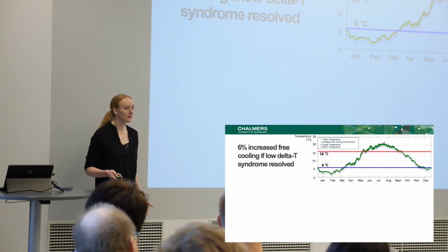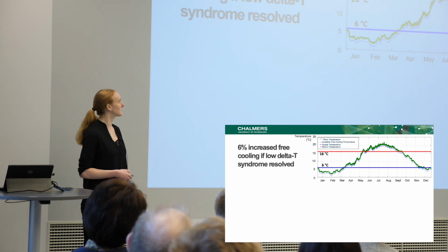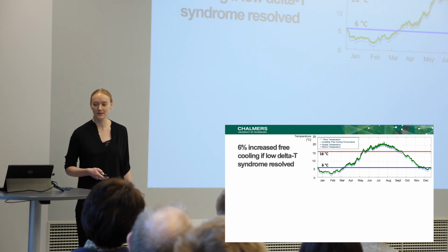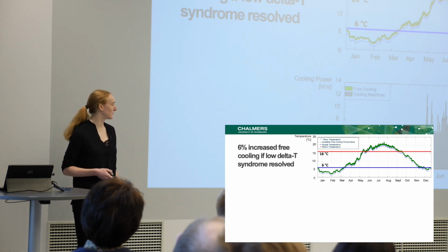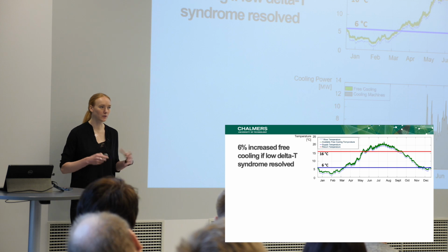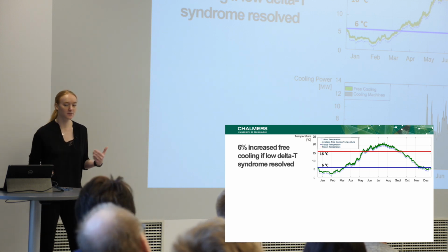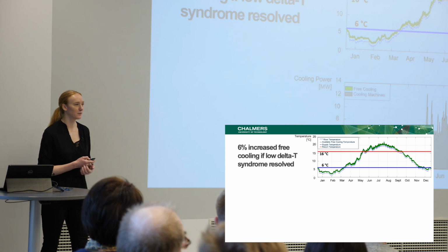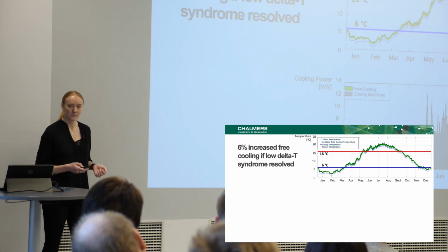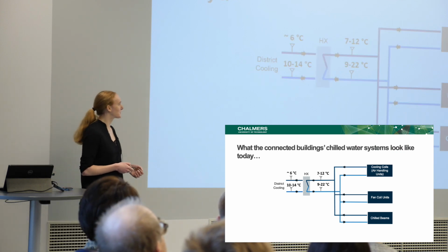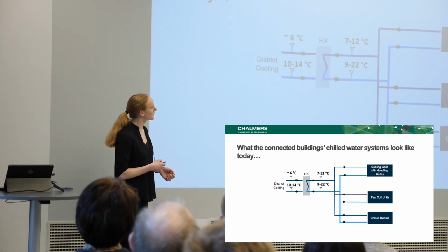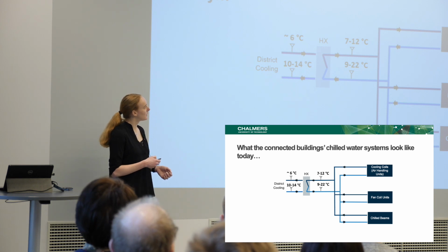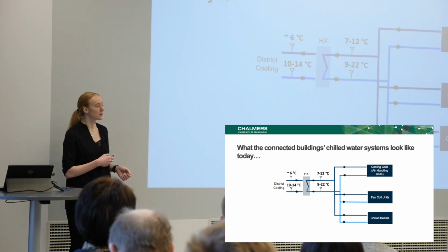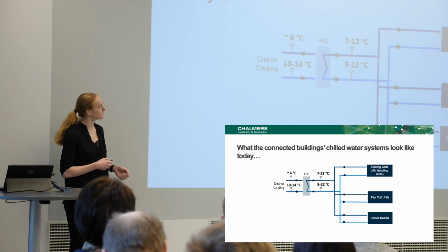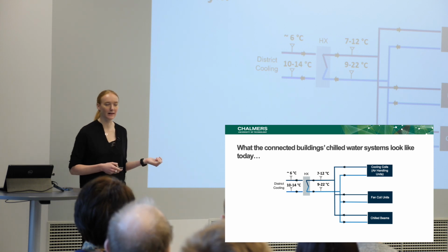Now, if the low delta T was to be resolved and 16 degrees were actually achieved on the return side, then the share of free cooling would jump up to 34% of the total production over the year, which is a 6% increase. So this is if the low delta T syndrome was resolved. But we know already from the results that the buildings use temperatures in this range in the summer, and it leads to return and supply temperatures. Well, the supply is always around 6, but the return temperature varies. This is throughout the whole year between 10 to 14, based on the previous graph.